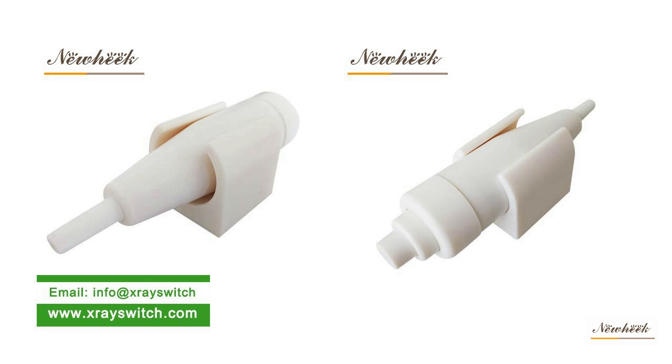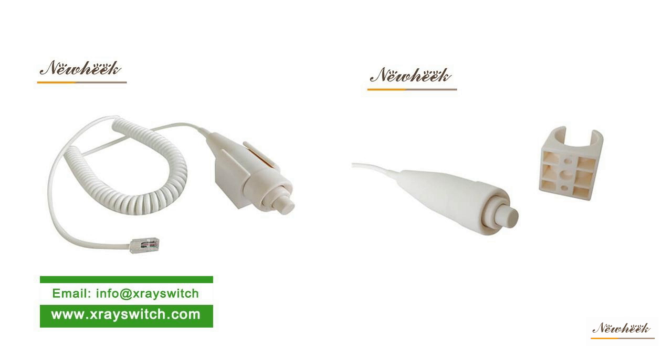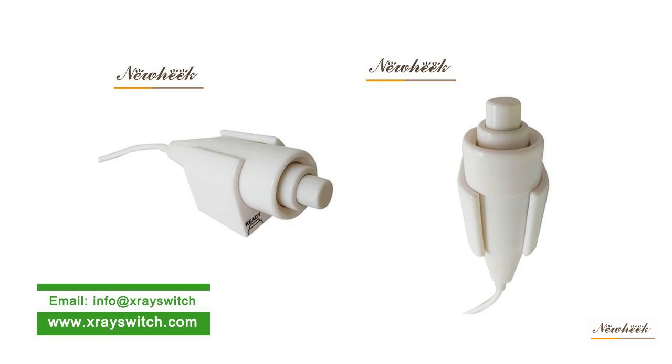Newheek develops and produces an X-ray hand switch for X-ray machine exposure, which replaces the traditional machine-type X-ray hand switch and avoids the disadvantage of machine-type switches that cannot work normally due to long-time contact oxidation.